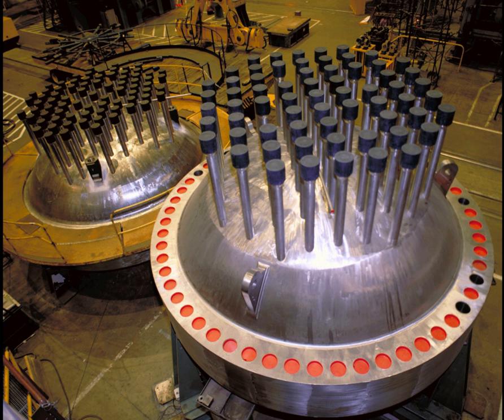After enrichment, the uranium dioxide powder is fired in a high-temperature sintering furnace to create hard ceramic pellets of enriched uranium dioxide. The cylindrical pellets are then clad in a corrosion-resistant zirconium metal alloy — zircaloy — which are backfilled with helium to aid heat conduction and detect leakages. Zircaloy is chosen because of its mechanical properties and its low-absorption cross-section. The finished fuel rods are grouped in fuel assemblies, called fuel bundles, that are then used to build the core of the reactor. A typical PWR has fuel assemblies of 200 to 300 rods each, and a large reactor would have about 150 to 250 such assemblies with 80 to 100 tons of uranium in all.